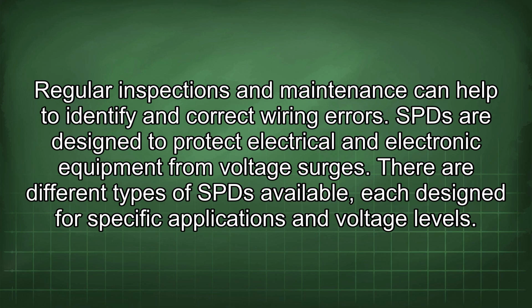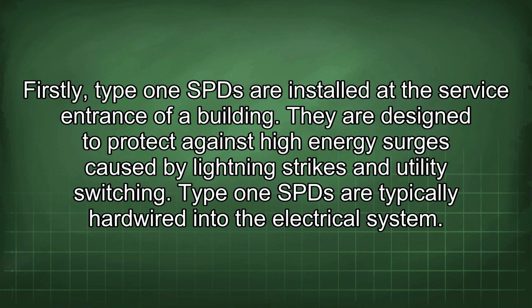SPDs are designed to protect electrical and electronic equipment from voltage surges. There are different types of SPD available, each designed for specific applications and voltage levels. Firstly, Type 1 SPDs are installed at the service entrance of a building. They are designed to protect against high-energy surges caused by lightning strikes and utility switching. Type 1 SPDs are typically hardwired into the electrical system.